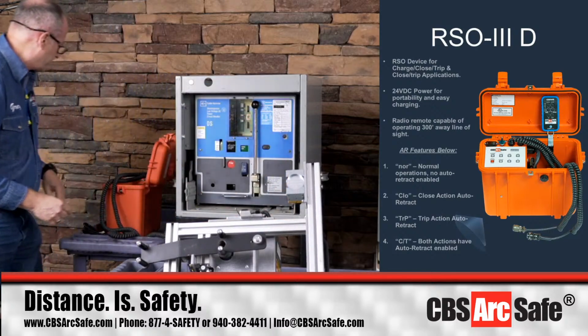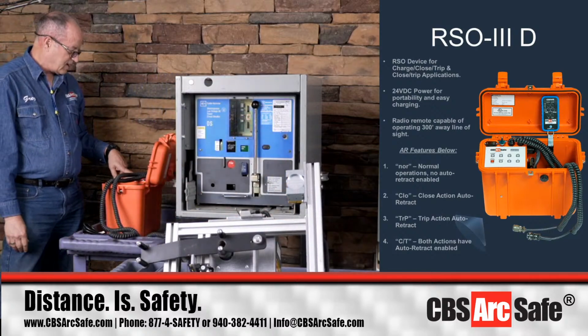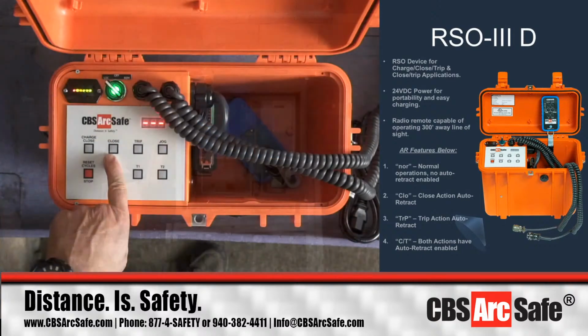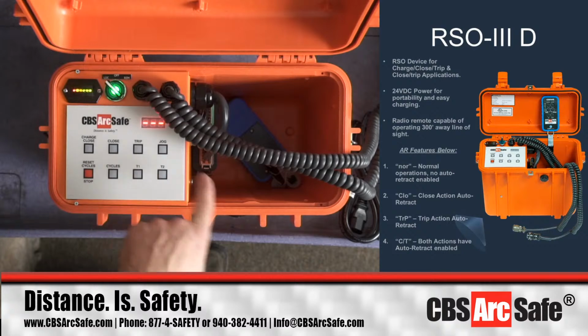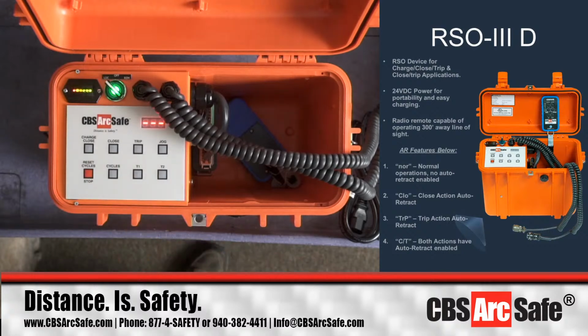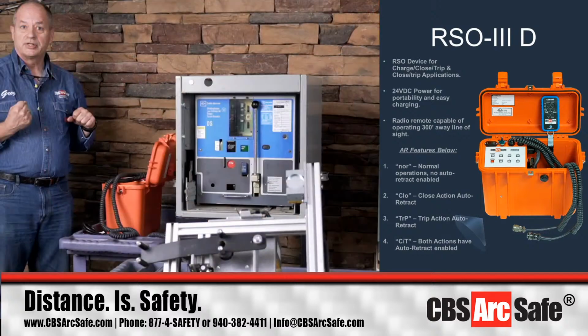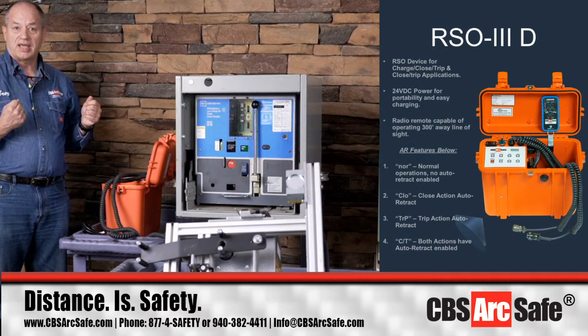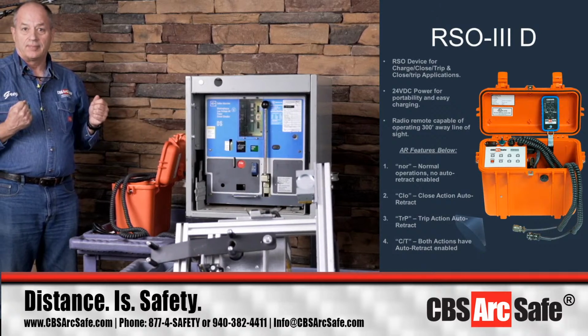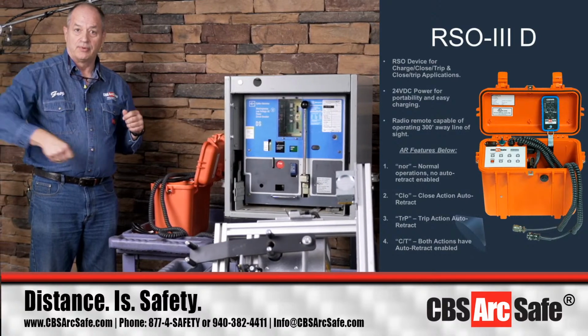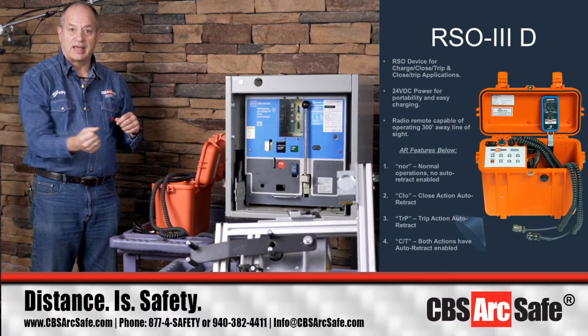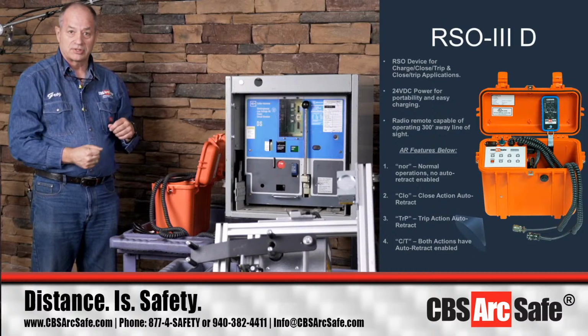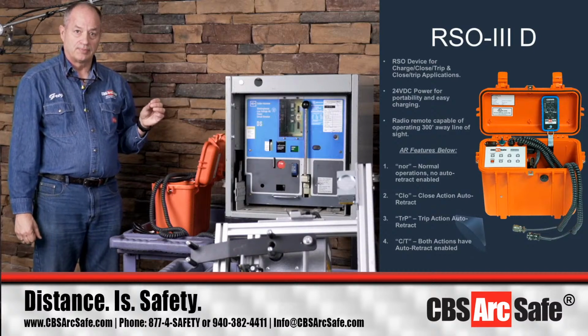All right. So somebody will ask the question, why do you have it labeled charge, close, trip, and jog? Okay. When we came up with these, you have the older breakers like a K-Line breaker. You just pull the handle down on the 2000 amp and below, and it closes at the bottom of the stroke. You've got a GE AK, AK-2, and the breakers in those families where you move the handle up to the right, bring it down, and it closes at the bottom of the stroke. So that's the reason it's called charge close.